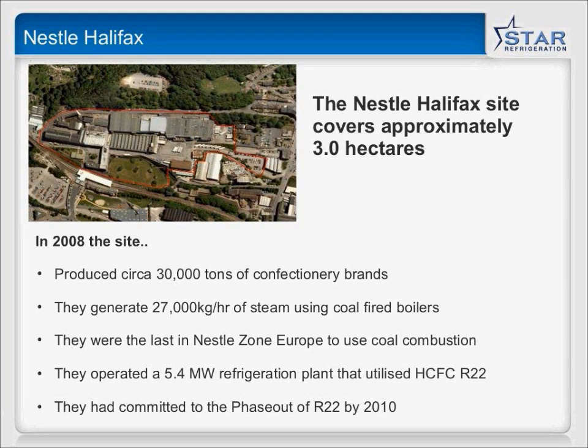The implication, and probably what's driving this question, is how much effort you should put into recommissioning the entire system. My answer is as much as you can possibly afford. When you change from one refrigerant to another, the oil type may need to change, and you need to think about the seals - that's a big part. There's absolutely no point putting new expensive refrigerant into a leaky system. Get it leak tight - spend the money getting it recommissioned to the best possible standard, then put the new refrigerant in. Otherwise, it's just going to piss out all over the place.